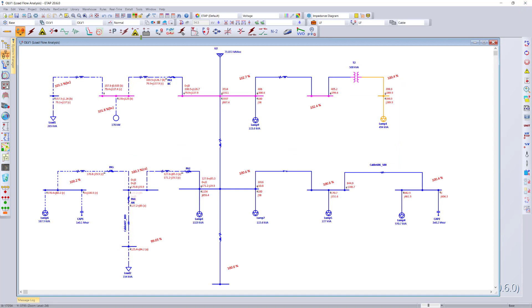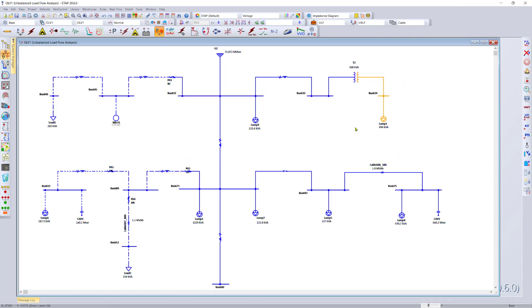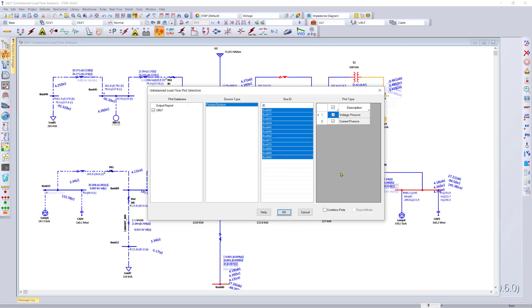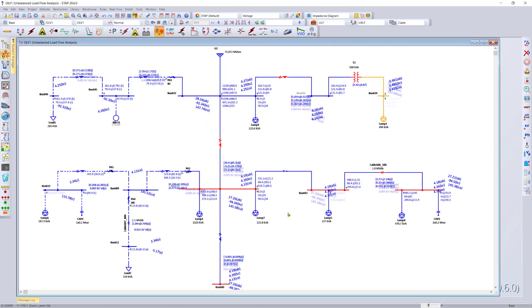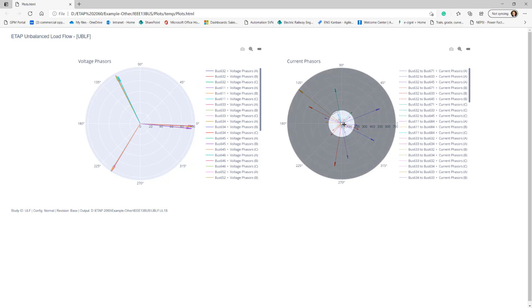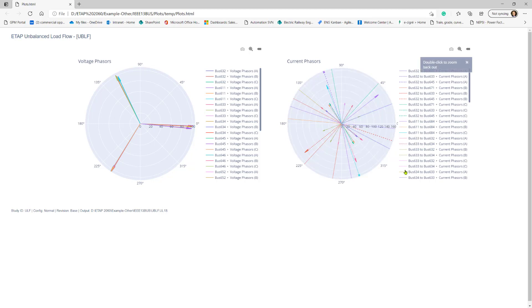With the plot analyzer, you can also go into unbalanced load flow module, run your unbalanced load flow program, and then bring up the plot analyzer from within this mode. You can then select between single or multiple buses at the same time and plot the voltage and current phasors. The program gives you a beautiful tiled view of all your voltage phasors as well as all the current phasors at the same time, allowing you to interact directly with the diagram and visualize more information.